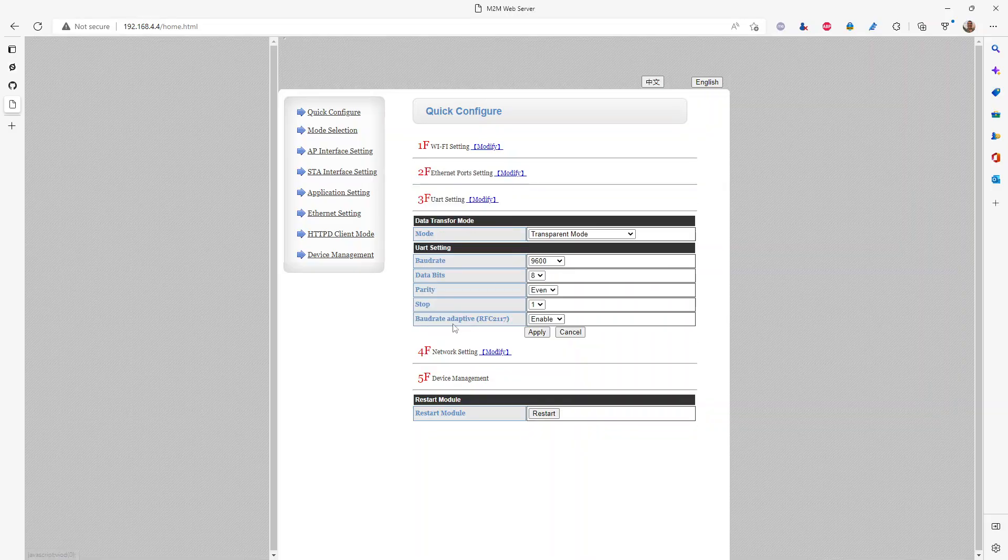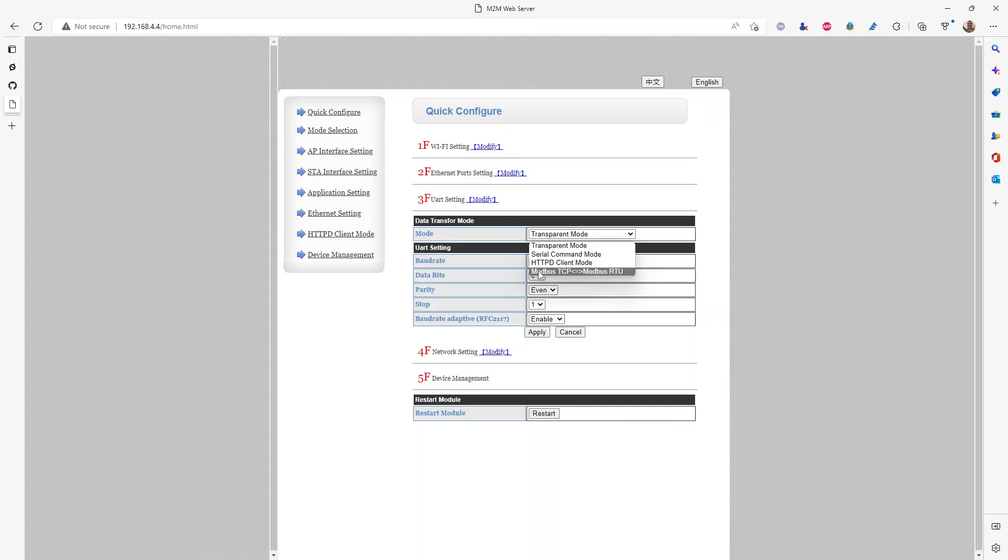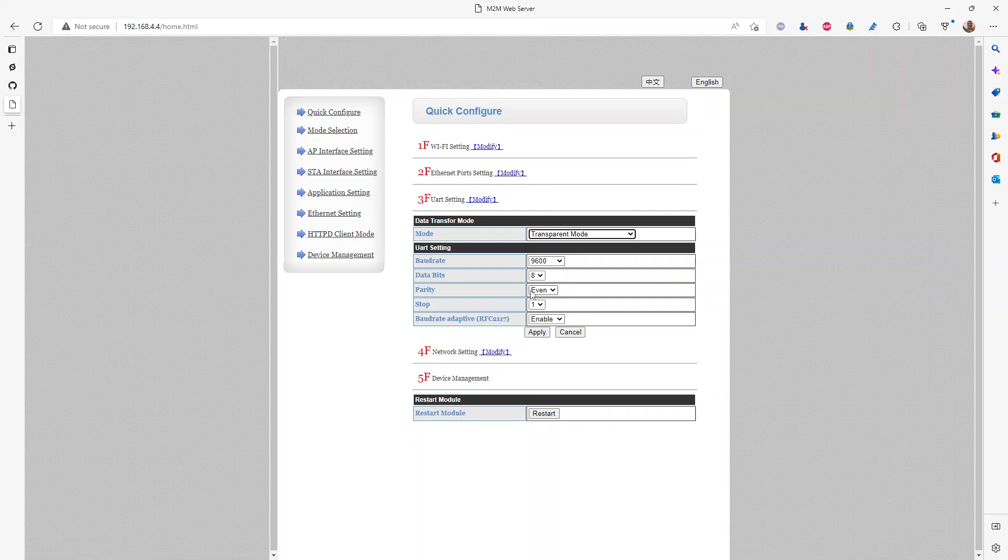In the UART setting, you'll want to do transparent mode. That gets the best performance between the Raspberry Pi and this device. If you pick a device that doesn't have transparent mode, Genmon does support Modbus over TCP, but there's additional checksums and overhead in wrapping the Modbus packet into a TCP packet a second time. So the transparent mode allows direct serial communication over TCP IP. We mentioned in a few other spots, you need to get some of the data from the generator directly, the baud rate and parity. So you'll need to configure it to look like this - 9600-8E1. And that will allow all of the communication you need between the generator and the device.